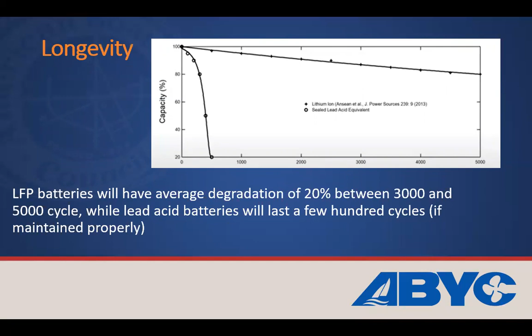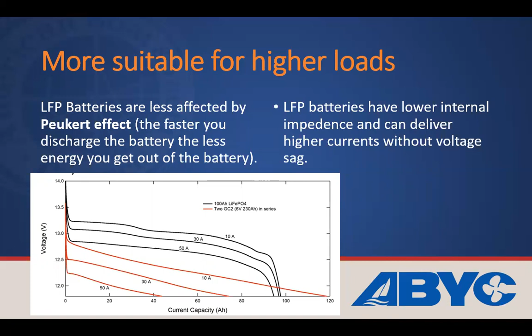Longevity - we talked about this before. The straight long line is lithium; it doesn't get memory or sulfation, and it lasts much longer. When you look at higher loads, lithium does better. The red are lead acids versus lithium ions, and this is chemistry - Peukert's effect comes in, affecting how quickly you can discharge while still maintaining voltage above critical levels. Charge time - lithium takes a faster charge, and this comes into play with how they're applied, where they're put, and how they're used.